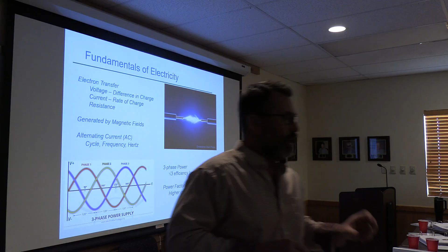If you start alternating the hertz, that's a little what Carlisle was saying. You start manipulating the frequency, you really can start manipulating the power and the way the motor operates as well. But I wouldn't do that with your gen set. I would do that rather with a controller like a drive.